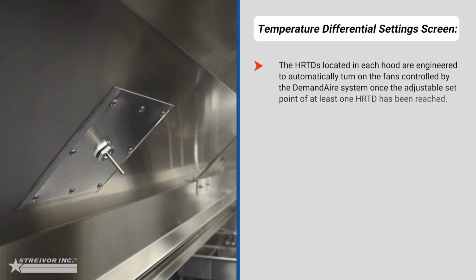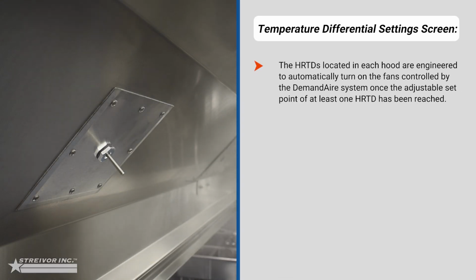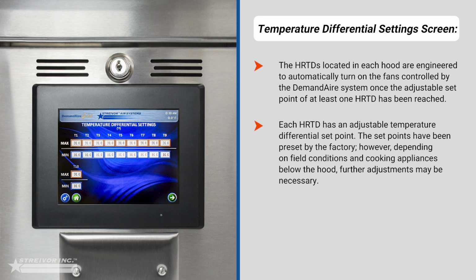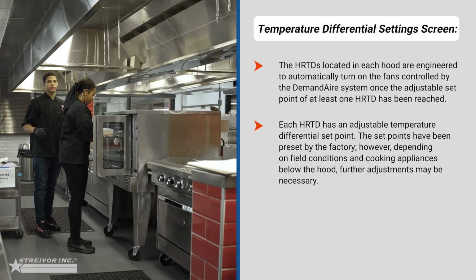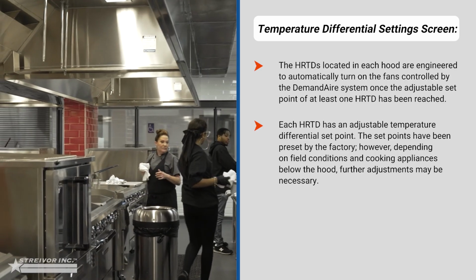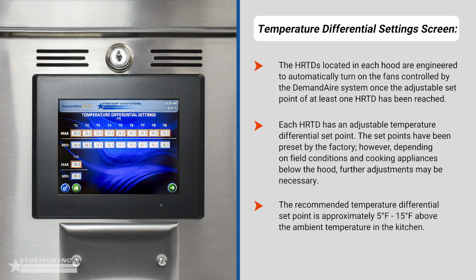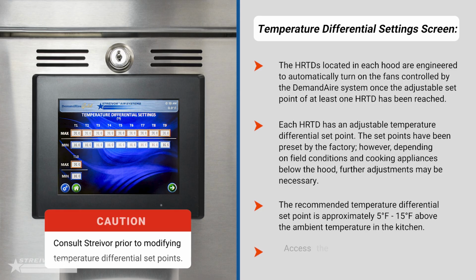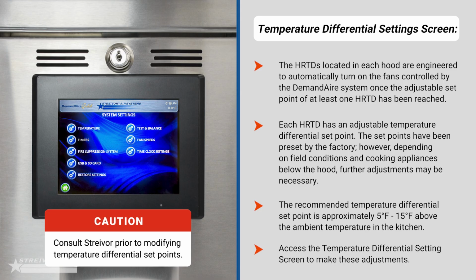The HRTDs located in each hood are engineered to automatically turn on the fans controlled by the DemandAire system once the adjustable set point of at least one HRTD has been reached. Each HRTD has an adjustable temperature differential set point. The set points have been preset by the factory. However, depending on field conditions and cooking appliances below the hood, further adjustments may be necessary. The recommended temperature differential set point is approximately 5 degrees to 15 degrees Fahrenheit above the ambient temperature in the kitchen. Access the temperature differential setting screen to make these adjustments.